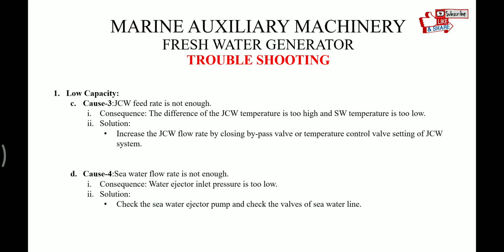Fourth cause for low capacity is seawater flow rate is not enough. Consequence: water ejector inlet pressure is too low. And the solution for that is check the seawater ejector pump and check the valve of the seawater line.